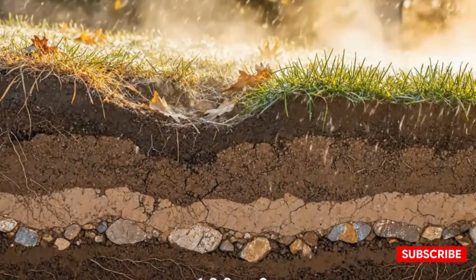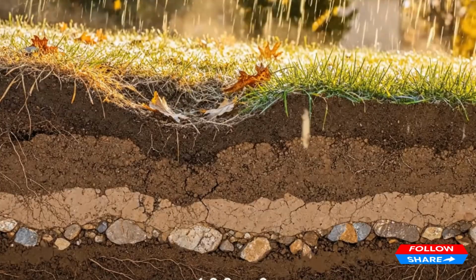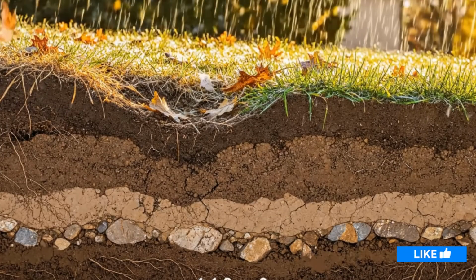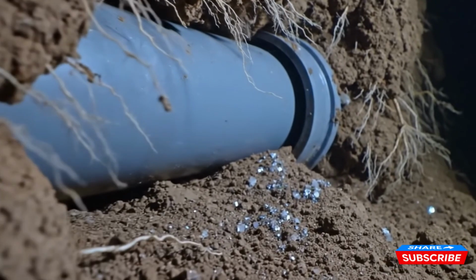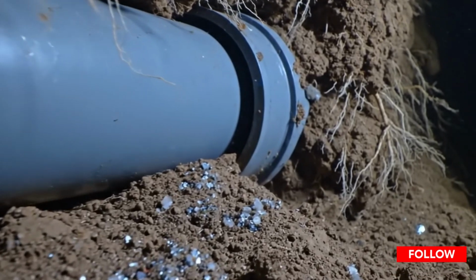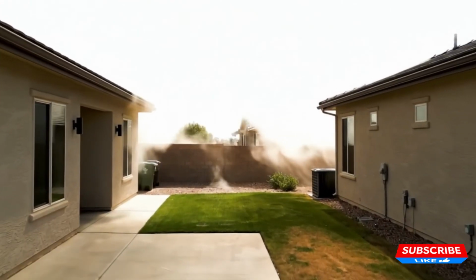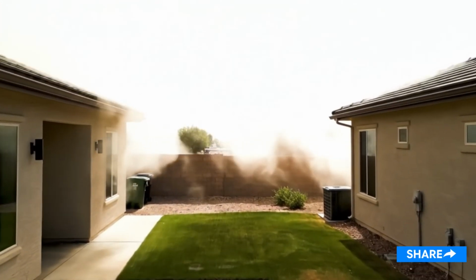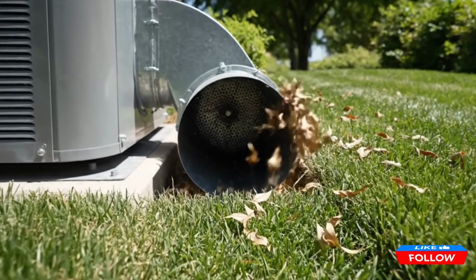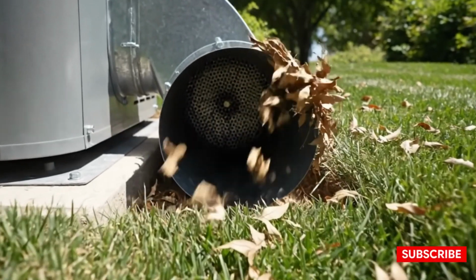Instead of running a compressor that draws thousands of watts, an earth tube can operate with a fan that uses only a tiny fraction of that. That's why this solution is so appealing. It's not magic, it's not experimental, it's simply heat exchange. Air moves, heat flows, the earth absorbs it. And when the design is done well, the performance can be impressive.